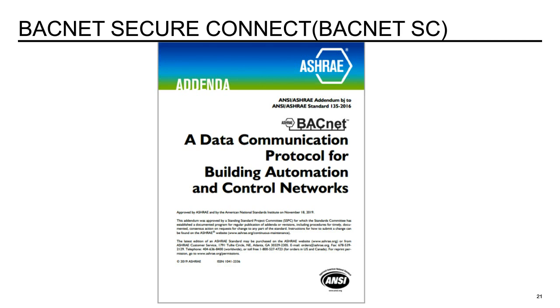BACnet SC is the first addendum to the BACnet standard that can be applied to previous versions of the standard. This means that older devices, if capable, can be updated to speak BACnet SC without revving them to the latest revision of the standard. This implementation is expected to accelerate the introduction of BACnet SC products into the market.